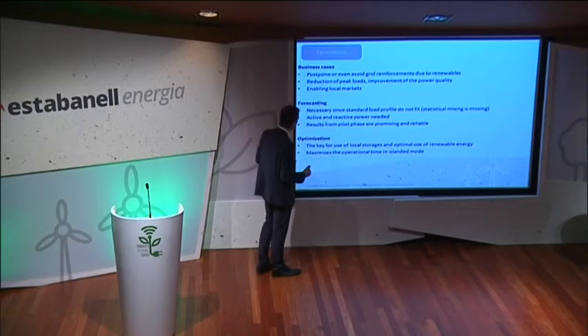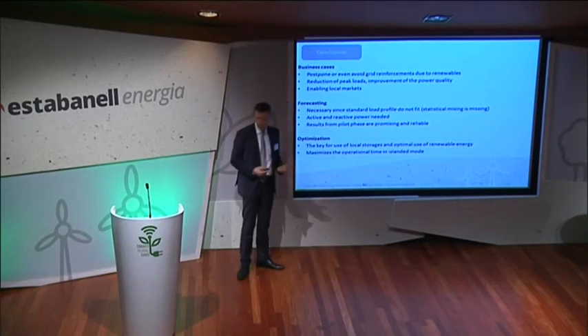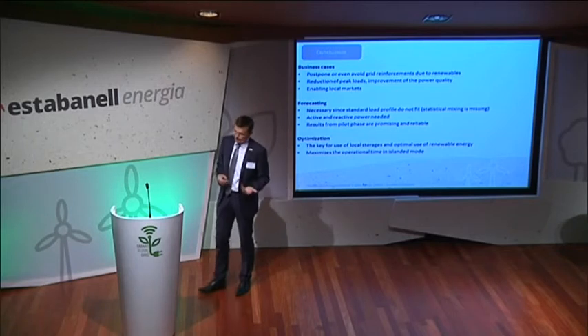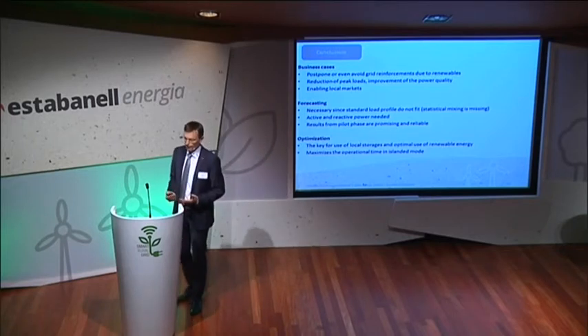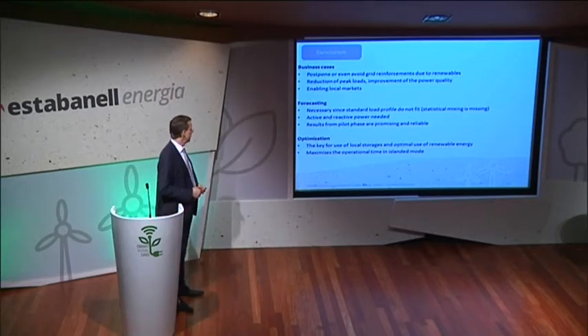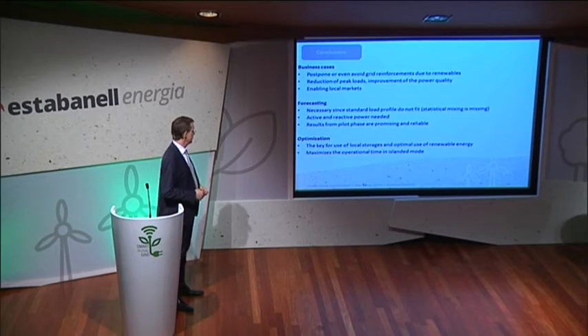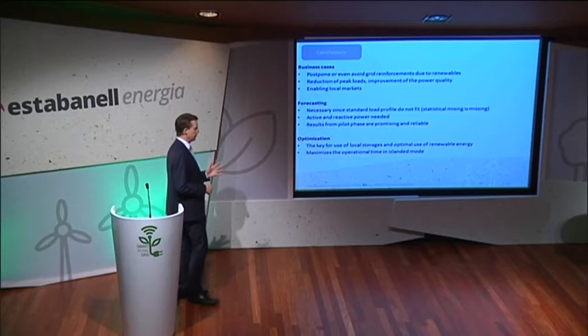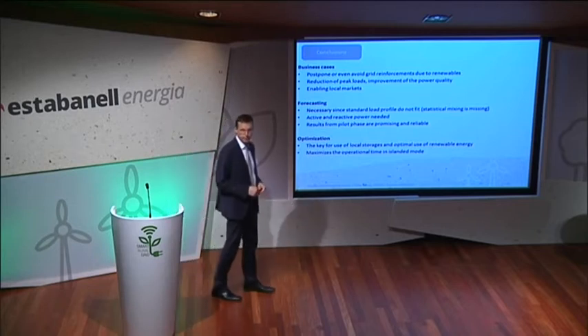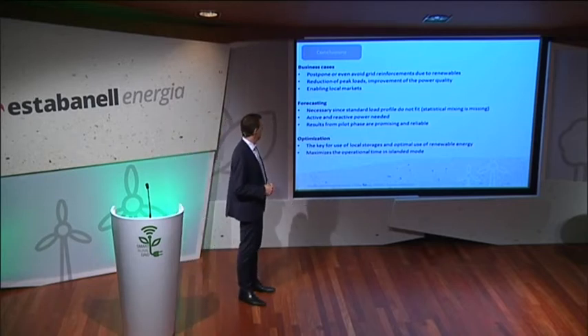Forecasting, we saw that it is necessary to do a forecasting, and even a bad forecast is better than a standard load profile in this case. We also saw that it is a very good idea to do this on the active and the reactive side, because we need the reactive side for voltage limitations, and the question of how much active power we can carry over a line.